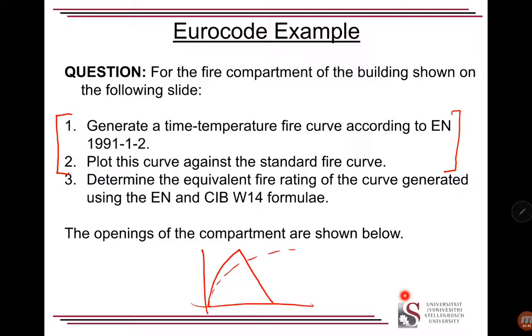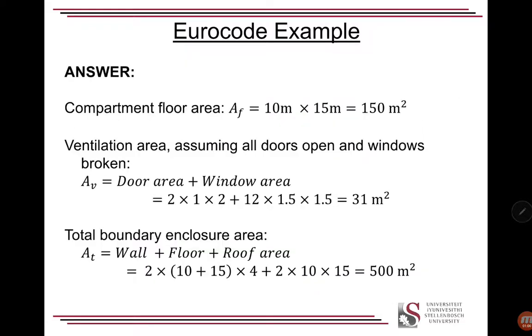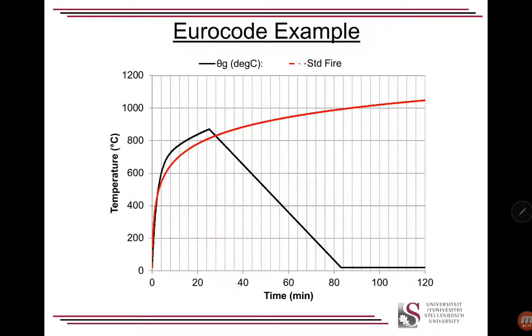And now we are going to determine the equivalent rating. So here is the enclosure. We've got two doors and twelve windows and various parameters. As I said, refer to the previous video which covers this example in more depth. Our floor area is 150 square meters, we've got 31 square meters of window, and a total boundary area of 500 square meters. That's wall, floor, and roof together, not excluding the window or the ventilation area. It's the total boundary area.